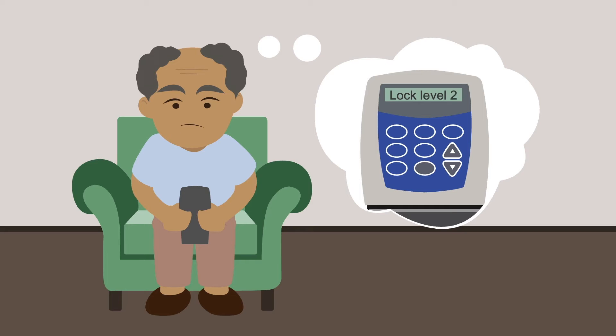Lock level 2 locks the settings so that patients can't change the continuous infusion and can only give themselves extra doses.